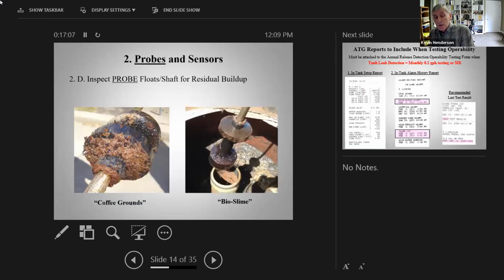And of course, this is one of the other issues that you want to be sure you look at, the residual buildup on the floats. You know, these floats stay in these tanks for a long time. And these days, with all the biofuels that we have and ethanol fuels, things happen inside tanks that are just really weird sometimes. Getting this kind of crud on your floats is never good. It's not a good thing, of course. So part of the annual ATG probe pulling operability test is cleaning these floats up, cleaning everything up, making sure it's all the way it should be.